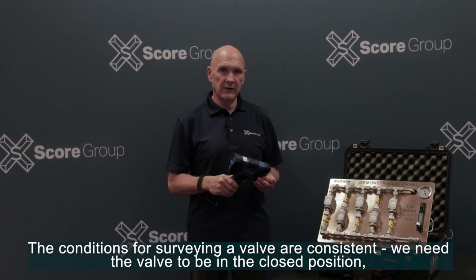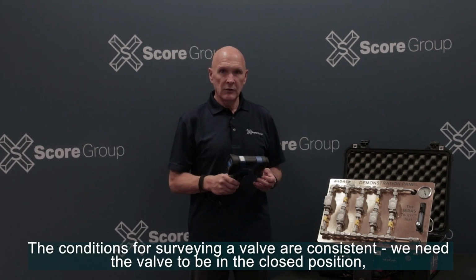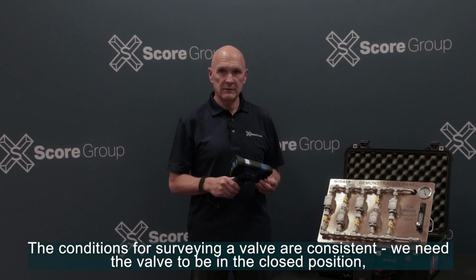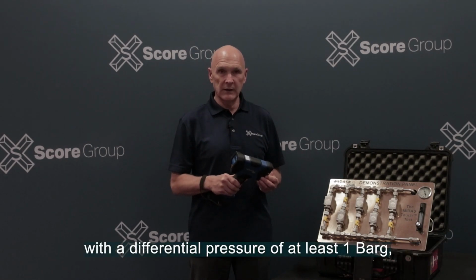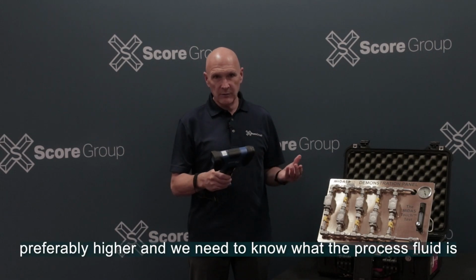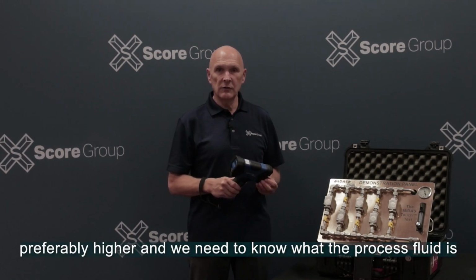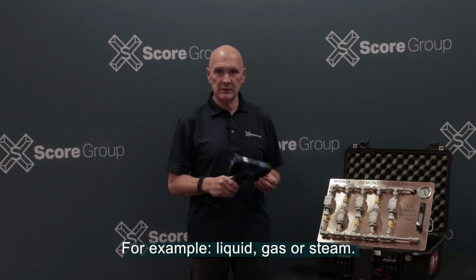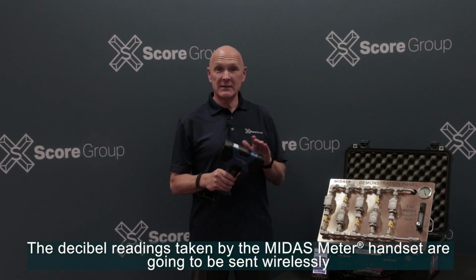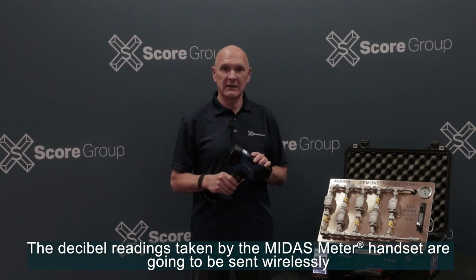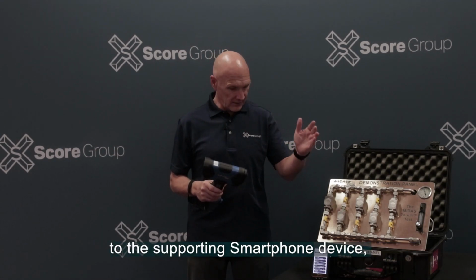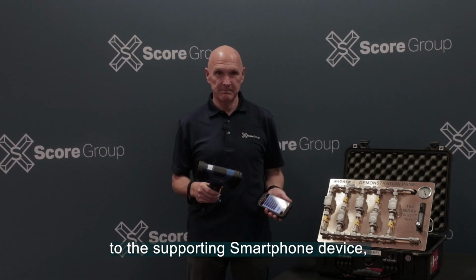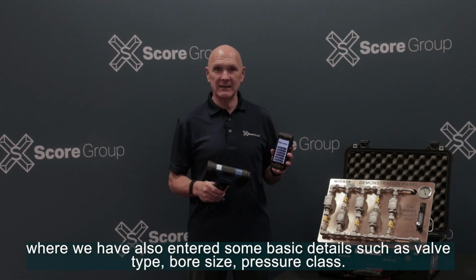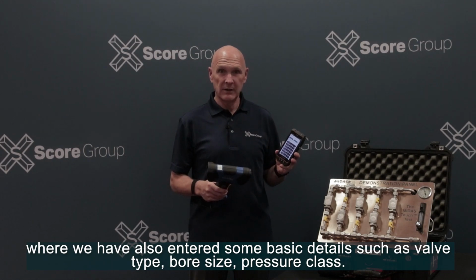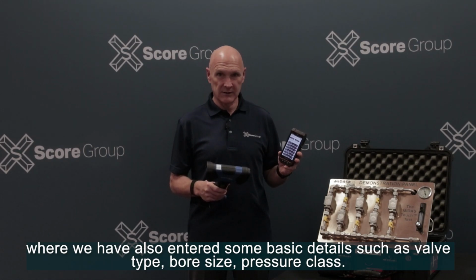The conditions for surveying a valve are consistent. We need the valve to be in the closed position with a differential pressure of at least 1 bar, preferably higher, and we need to know what the process fluid is, for example, liquid or gas or steam. The decibel readings taken by the MIDAS meter handset are going to be sent wirelessly to the supporting smartphone device, where we've also entered some basic details such as valve type, bore size and pressure class.